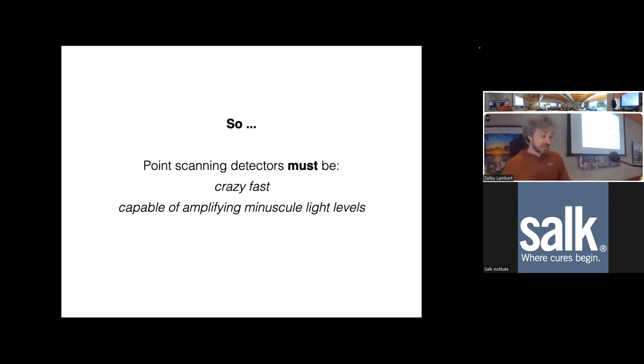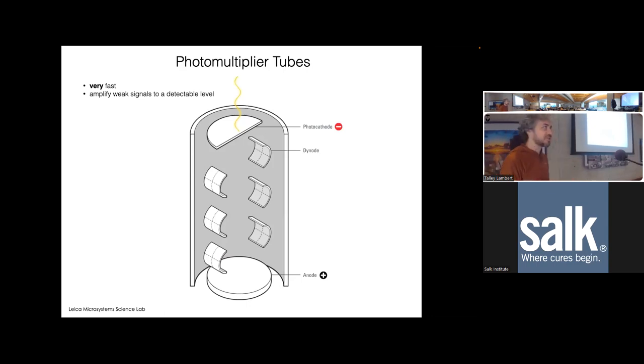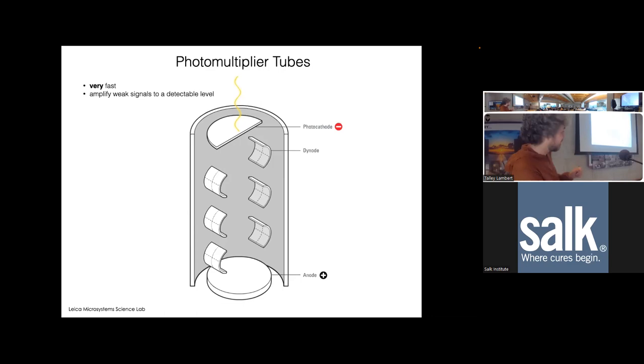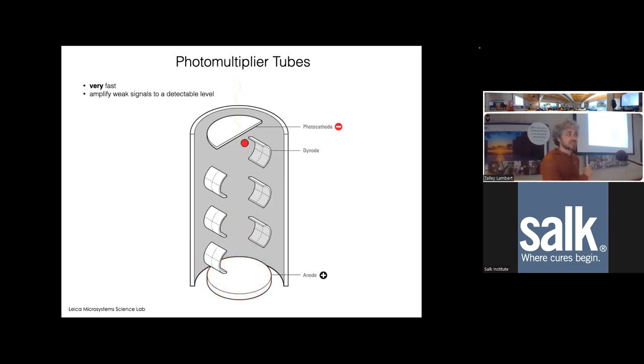PMTs use this multiplicative process. Why can't we just detect a single electron in the first place? A phenomenon called read noise or detector noise makes it very hard to confidently detect one electron - there's noise in the system. So what we need to do, if we want to be really confident that we detected that single photon, is multiply it. This multiplication process happens super fast and is capable of amplifying super weak signals collected in tens of nanoseconds or microseconds to some detectable level.